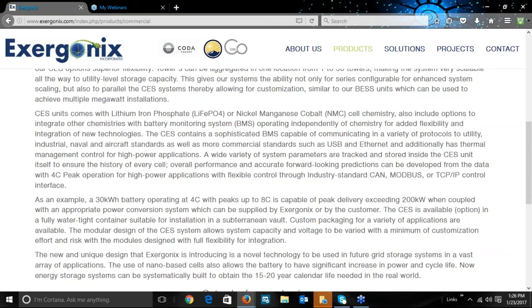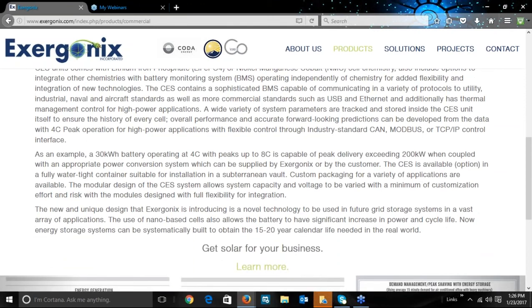A wide variety of system parameters are tracked and stored inside the CES unit itself to ensure the history of every cell. Overall performance and accurate forward-looking predictions can be developed from the data, with 4C peak operation for high power applications, with flexible control through industry standard CAN, Modbus, or TCP/IP control interface. As an example, a 30 kWh battery operating at 4C with peaks up to 8C is capable of peak delivery exceeding 200 kW when coupled with an appropriate power conversion system, which can be supplied by Exergonix or by the customer.